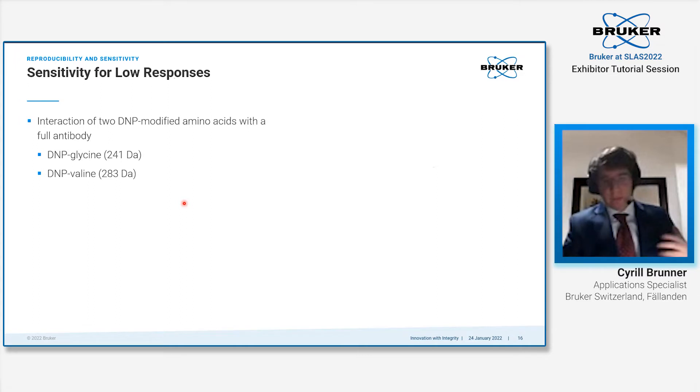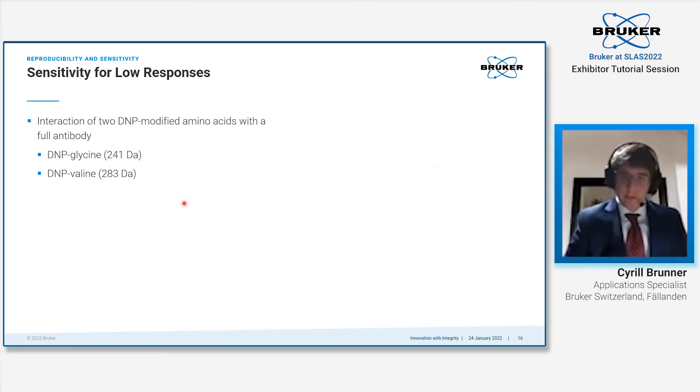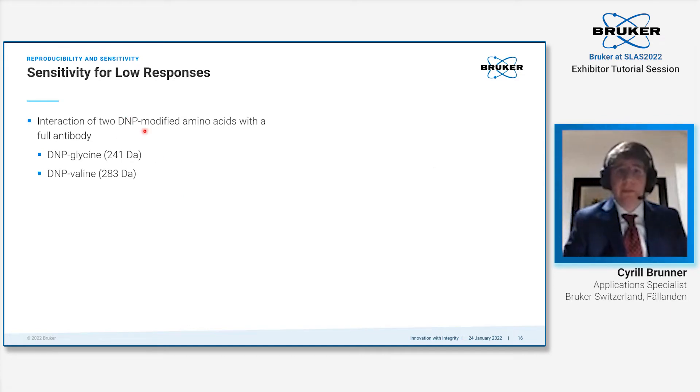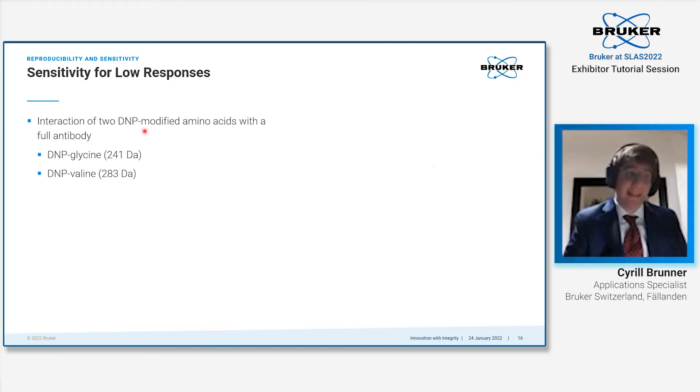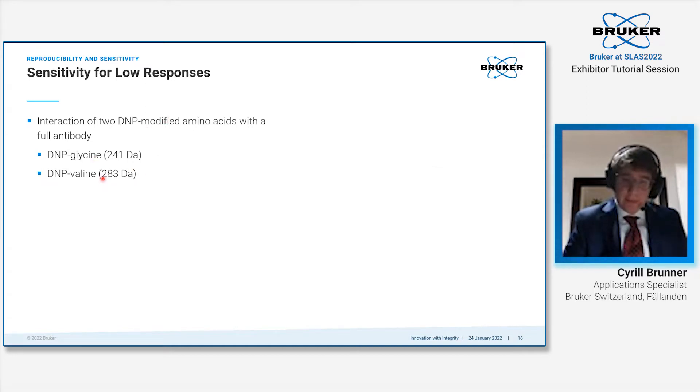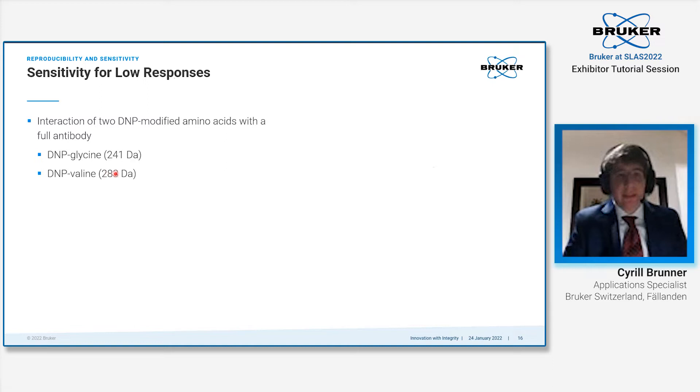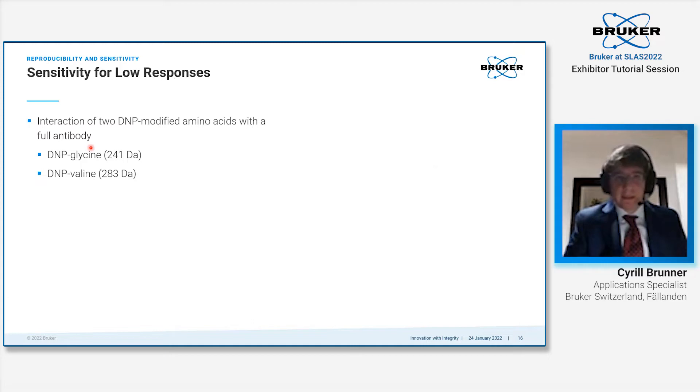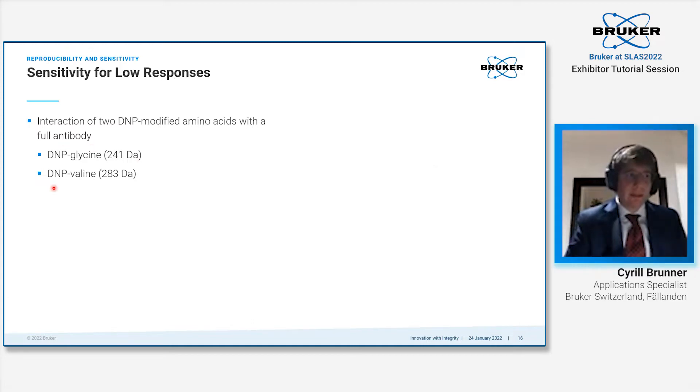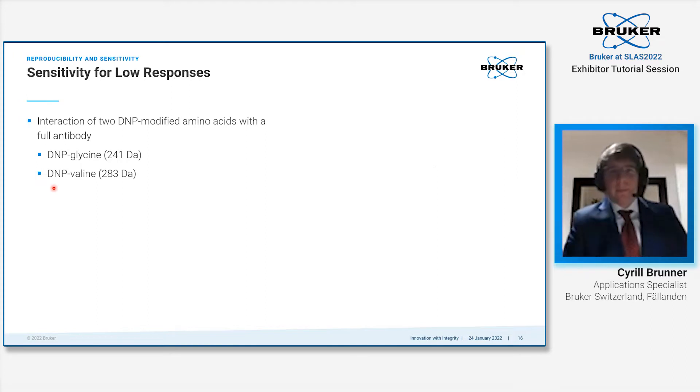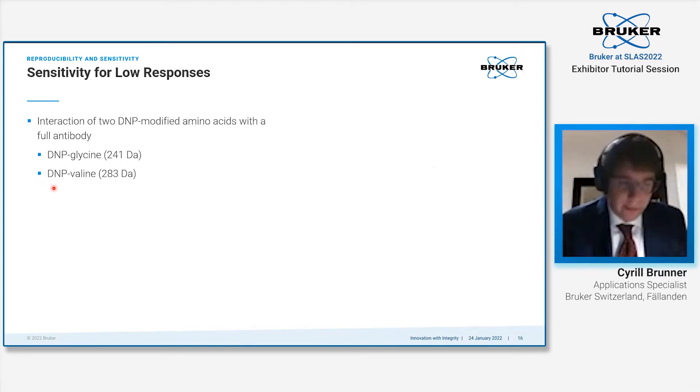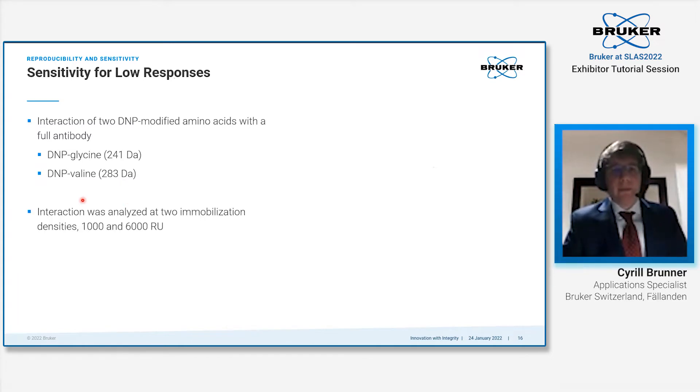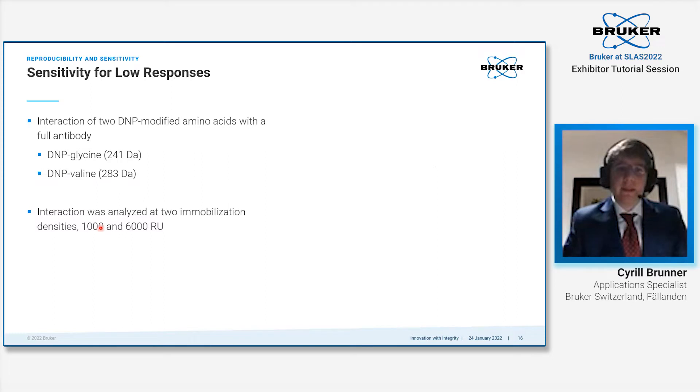The second important aspect for an SPR system, especially when it wants to be used for small molecule research, is its sensitivity. We tested two DNP modified amino acids against a large protein—in this case, an antibody. These DNP modified amino acids have a molecular weight of 240-280 Dalton against an antibody of 150 kilodalton. Why is that important? The lighter a compound is, the less signal it will give, especially when the target is accordingly heavy and the difference between them is very large.